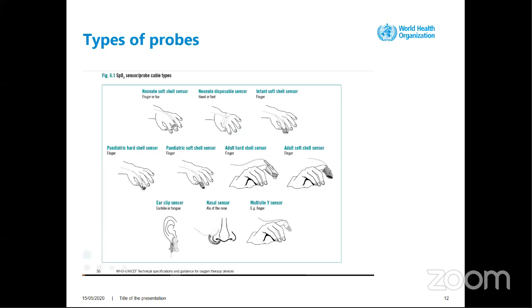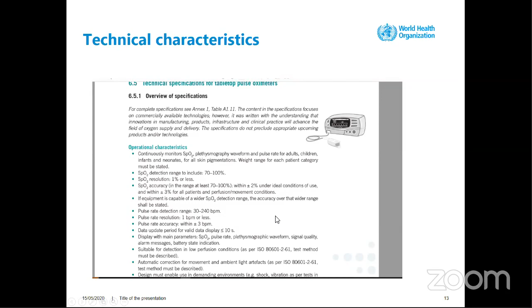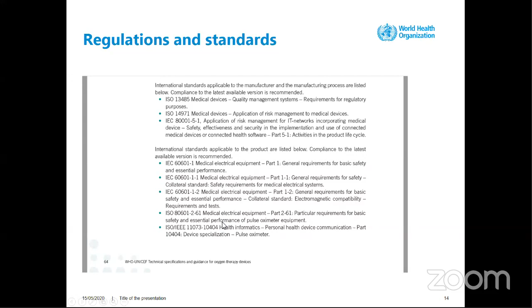We do have the technical specifications. For example, the SpO2 detection range should include 70 to 100%. The resolution should be 1% or less, and the accuracy within plus or minus 2% under ideal conditions. We know there are others that are 5% or so, but that is too much to make a really good assessment of the patient. We have the standards they should comply with. Besides the quality management ones like ISO 13485, we have the special ISO 80601-2-61, particular requirements for pulse oximeter equipment, within medical electrical equipment. This is absolutely indispensable.